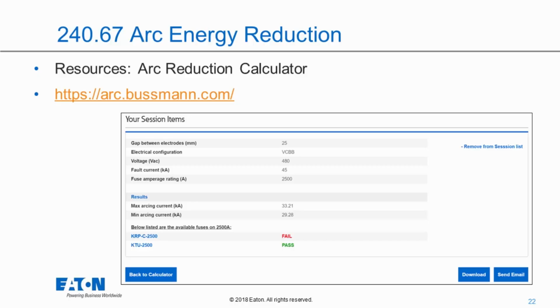We show a maximum and a minimum. The reason we show the minimum is if you look in IEEE 1584, it basically recommends taking 85% of the arcing current value to make sure that you're clearly within the time current curve for the required clearing time. And here we give you two options for this. We have our KRP-C 2500, which is our time delay class L, and we have a KTU 2500, which is our fast acting. And as you can see, provided you use the KTU 2500, you do not have to use any additional technology. If you use the KRP-C 2500, then you'd have to look at additional technology.